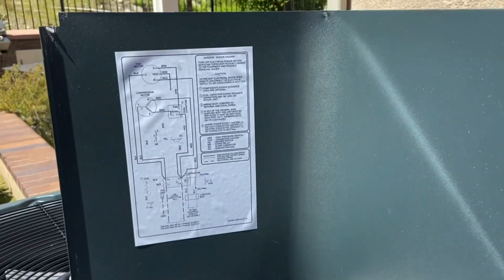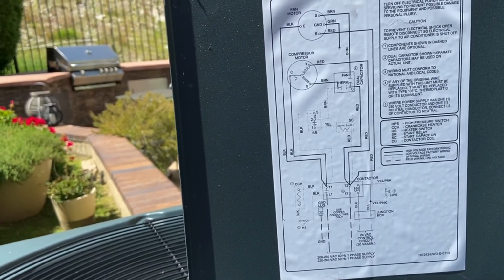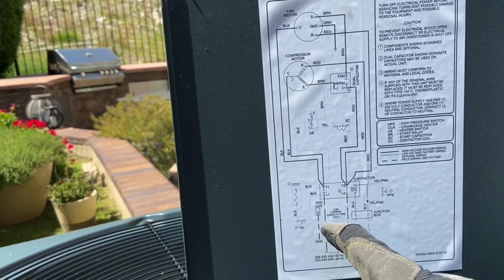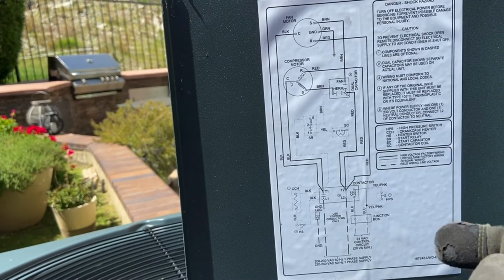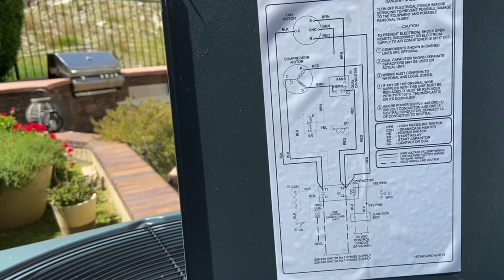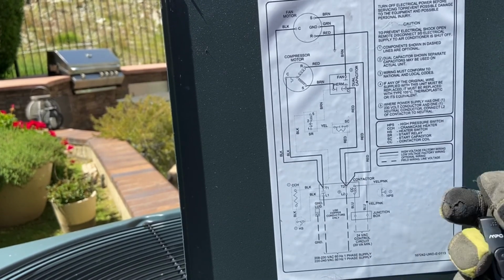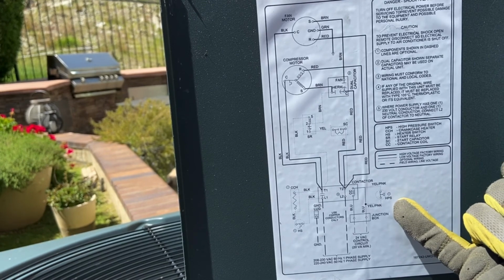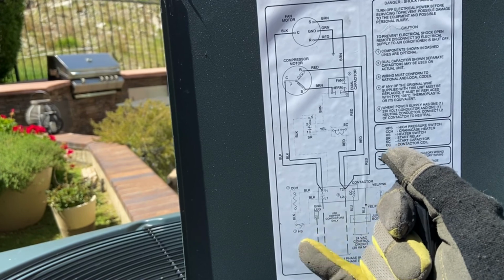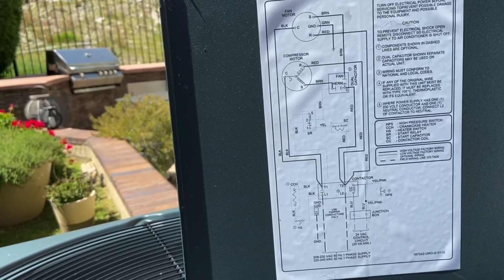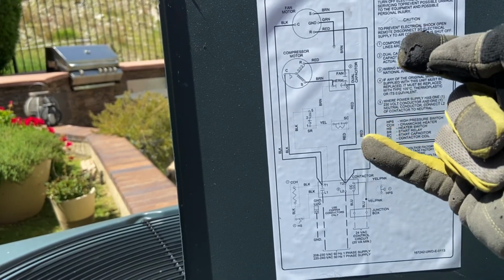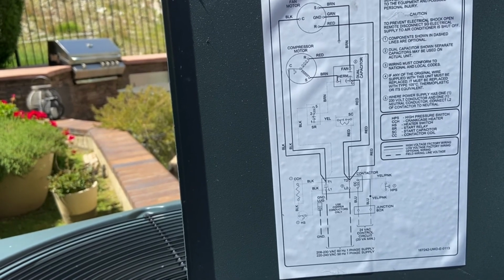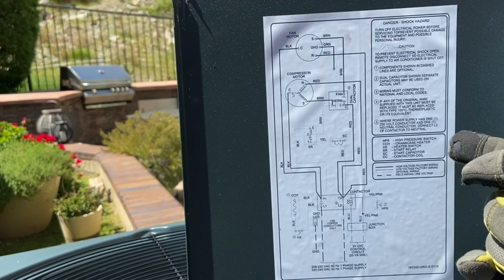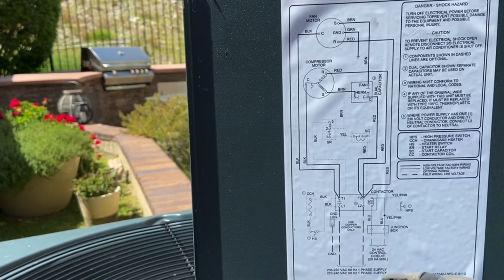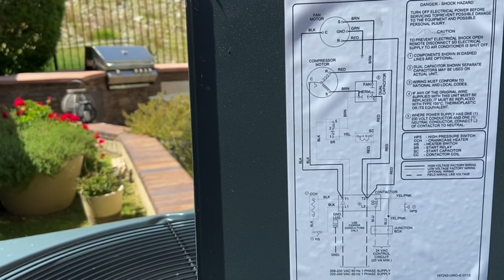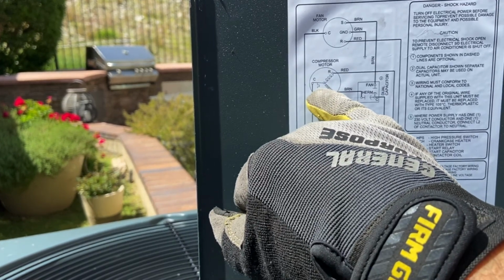Also want to take a look at the schematic for this unit. Pretty simple. It shows my high voltage wiring coming in with the dashed lines. My dark thicker lines are my high voltage. All the thinner solid lines are my low voltage. It looks like an optional high pressure switch, and an optional crankcase heater with a temperature based switch to open and close that and energize or de-energize it. Neither of these options are in here. Start capacitor, looks like a potential relay. None of that is part of this unit, but they are options, just not included. I've got my legend over on this side, which explains what all the acronyms are. You can see my start winding and my run winding for my compressor, and the thermal overload inside my compressor.